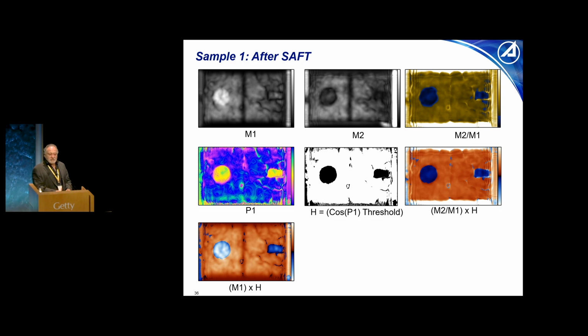We also purchased the ultrasonic scanning equipment from the vendor, which gave us the code to their machine so that we can reprogram it, because we wanted all of this to be done in real time, not post-processed. And we also attached string encoders so that the technician can use it freehand with 2 strings attached to a transducer. That way, each string gives you its length, and we can triangulate the position and have a monitor displaying in real time, just like a coloring book, the areas of good and bad. So something that was almost impossible, we made as easy as a child's coloring book.